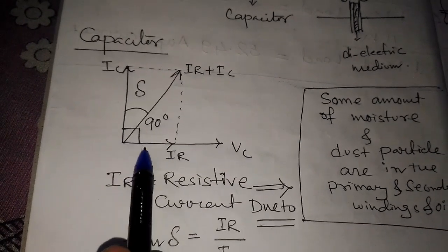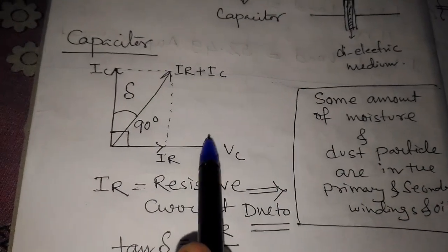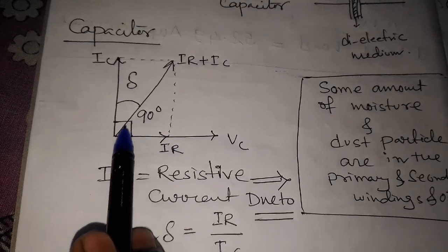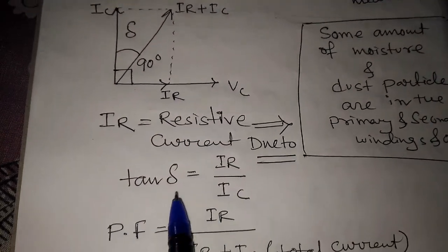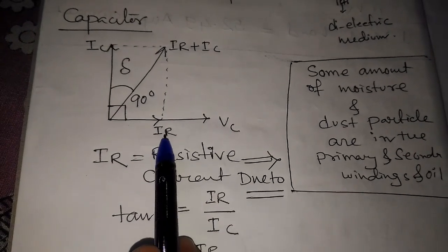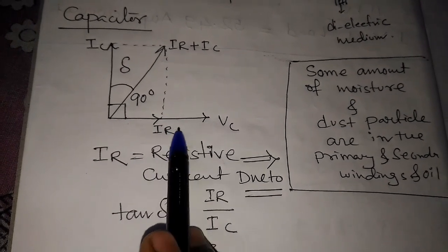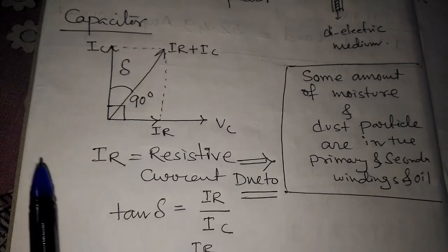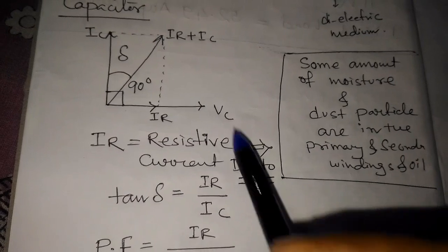For a pure capacitor, we get an angle of 90 degrees between voltage and current — the current leads the voltage by 90 degrees. In the case of the Tan Delta test, if we apply some voltage, some resistive current will flow through the winding. This resistive current will decrease the angle from 90 degrees.